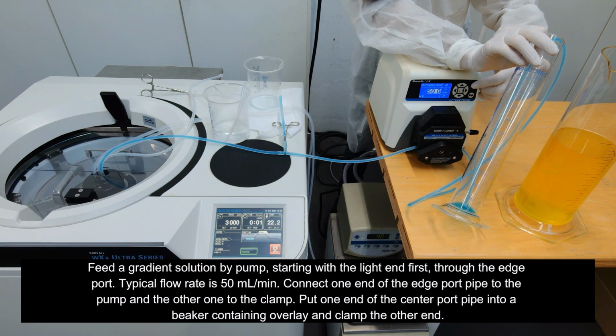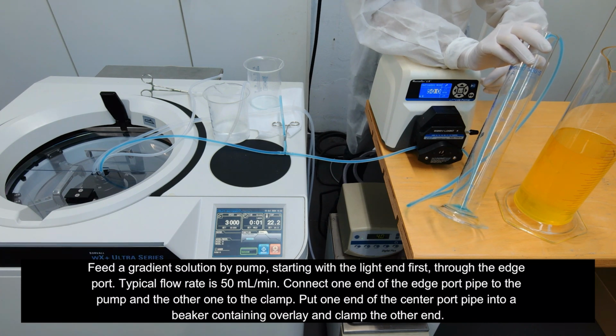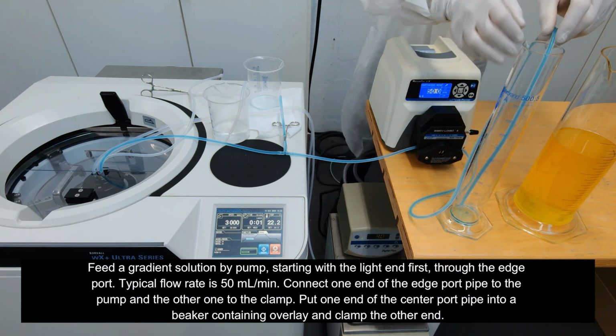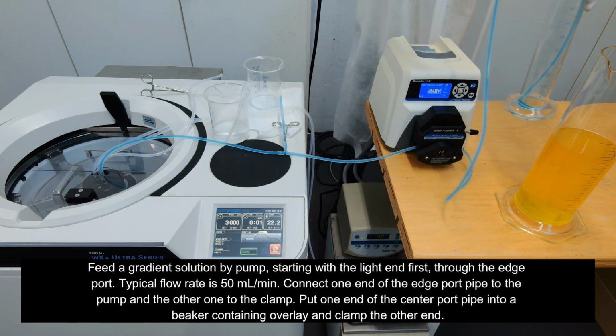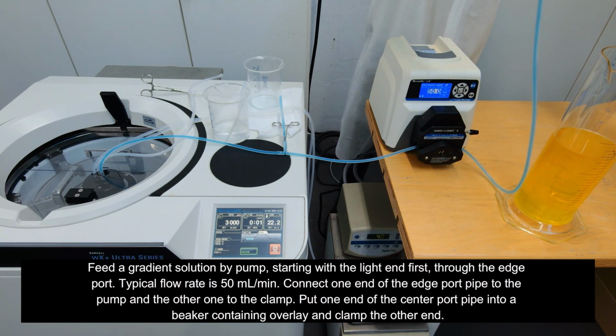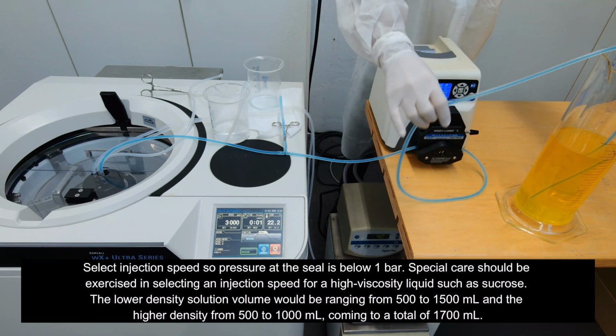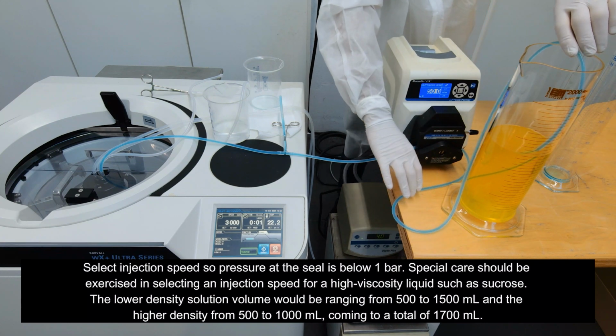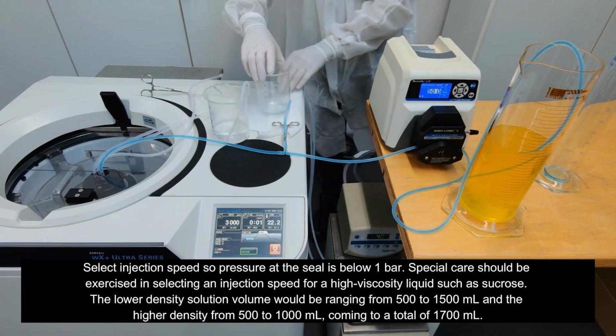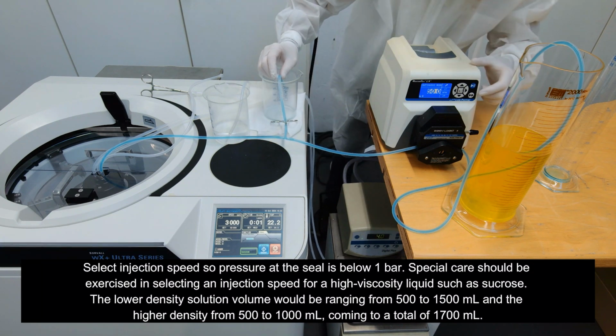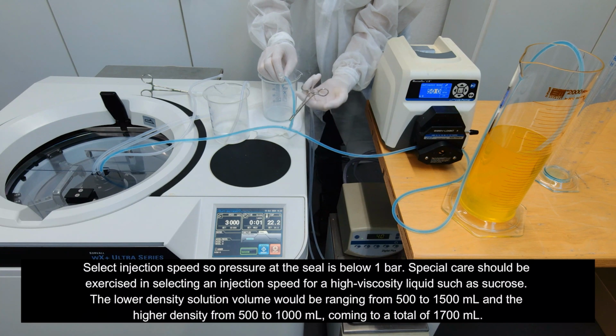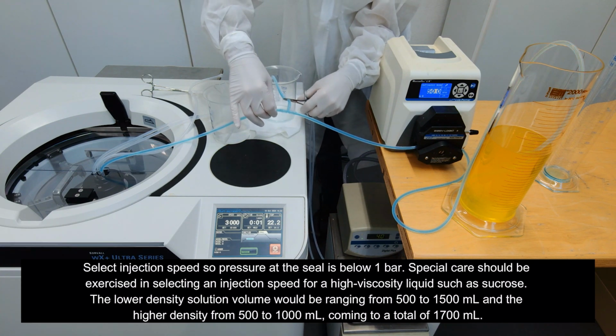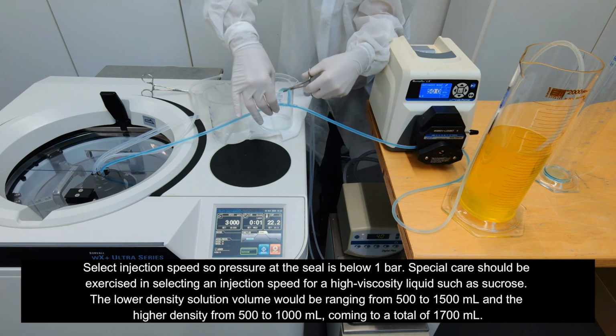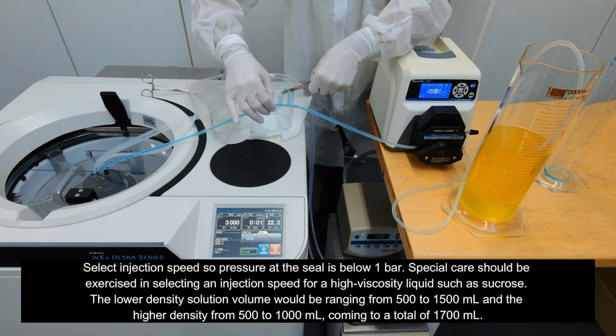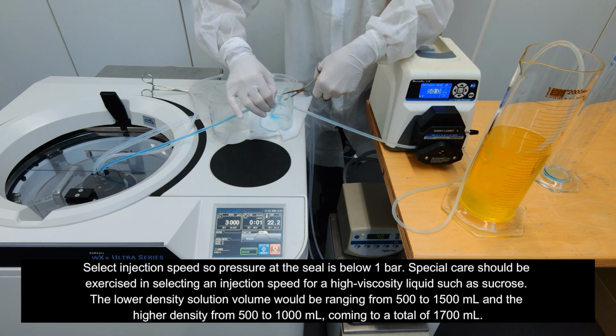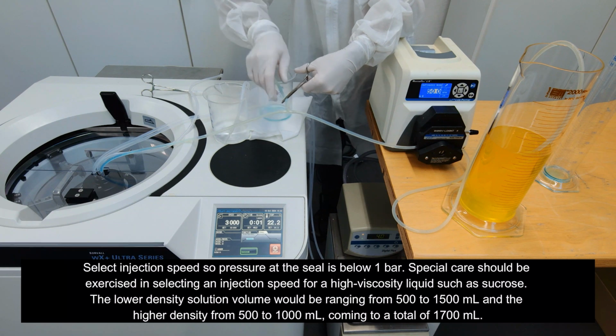Connect one end of the edge port pipe to the pump and the other one to the clamp. Put one end of the center port pipe into a beaker containing overlay and clamp the other end. Select injection speed so pressure at the seal is below 1 bar. Special care should be exercised in selecting an injection speed for a high viscosity liquid such as sucrose. The lower density solution volume will range from 500 to 1500 ml and the higher density from 500 to 1000 ml, coming to a total of 1700 milliliters.